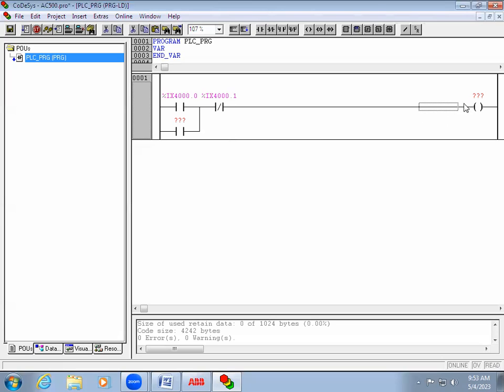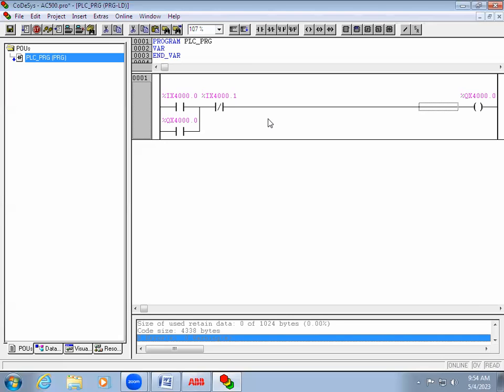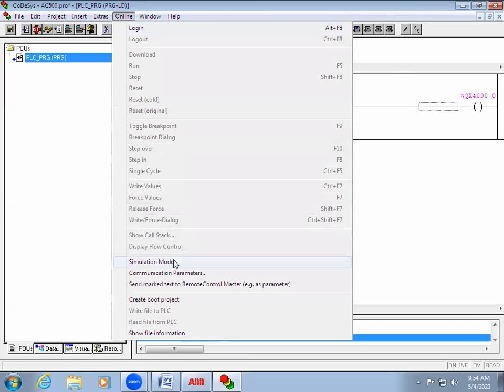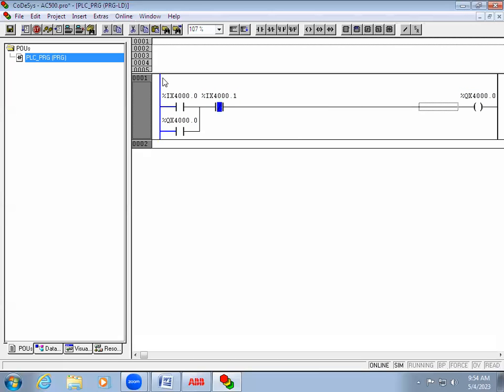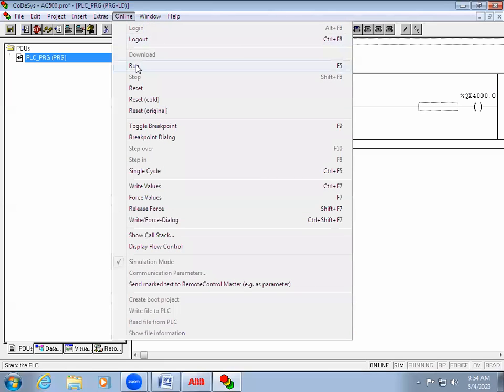The start input address is %IX4000.0, the stop input is %IX4000.1, and the output coil is %QX4000.0. Once the program is done, go to Project > Build to compile and check for errors. To test online, first select Simulation Mode, then Online > Login. At the bottom you can see it shows 'Online' and 'SIM'. It is not in run mode yet, so go to Online > Run.